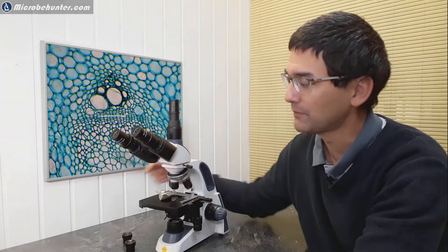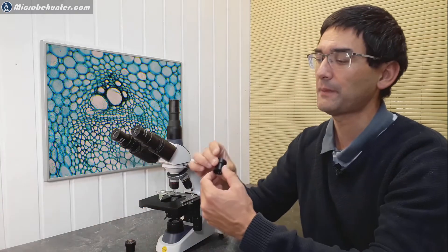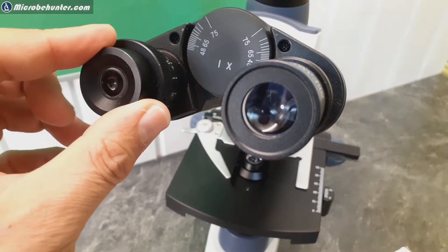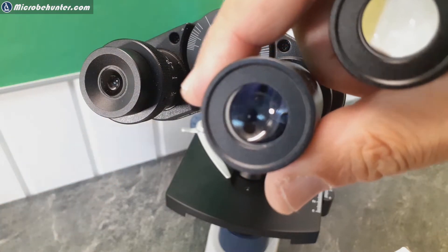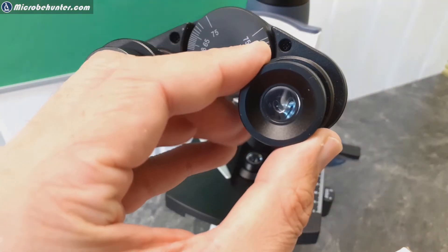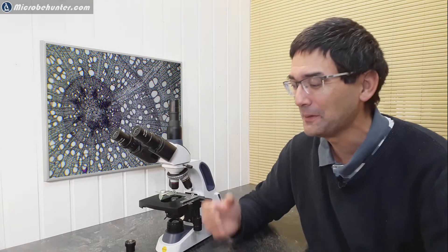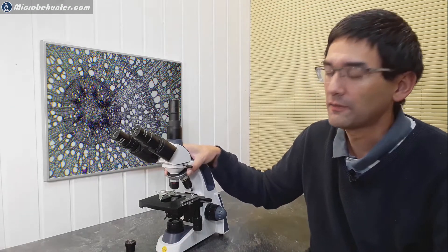But it's also possible to exchange those eyepieces. These are eyepieces magnifying 25x, and when you connect them you get 25 times 100 = 2500x maximum total magnification. I personally think that 1000x is really the maximum that anyone would ever want to use, but in any case it's possible to go up significantly more.